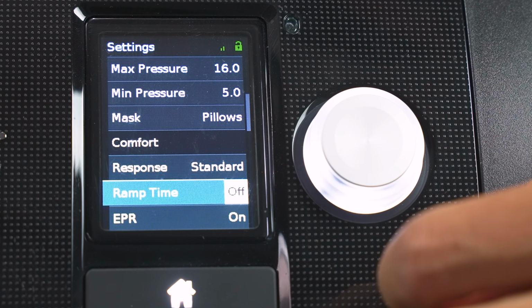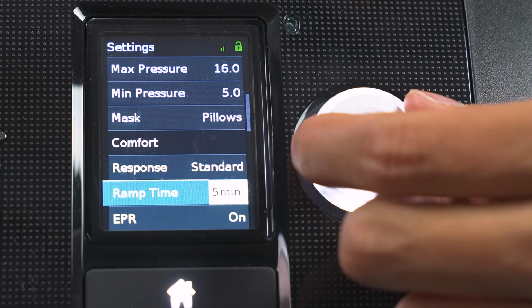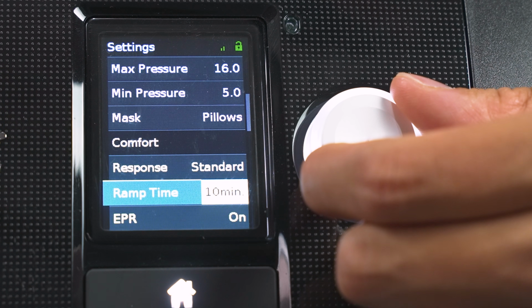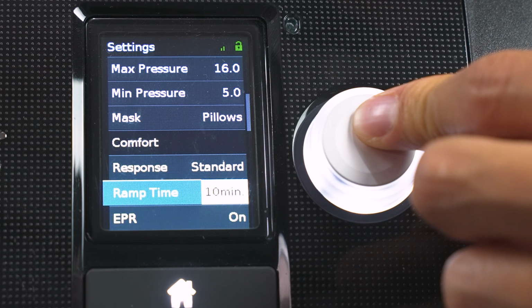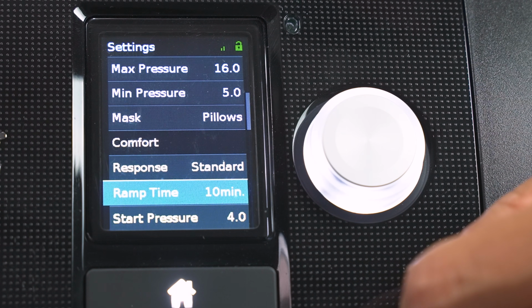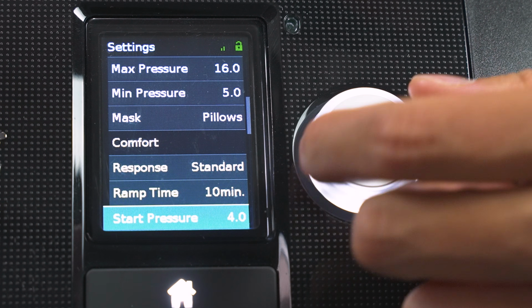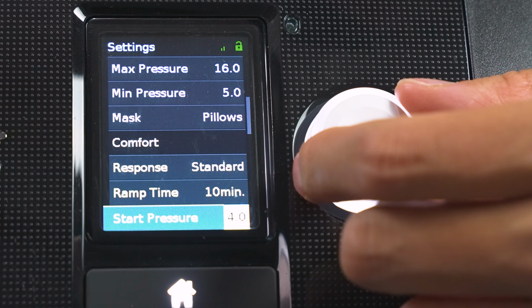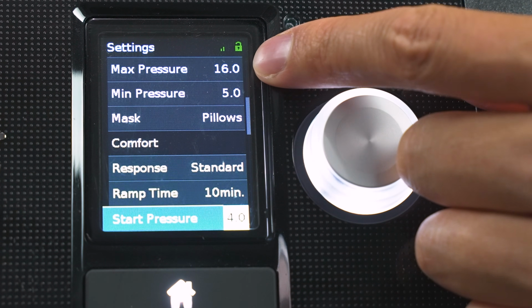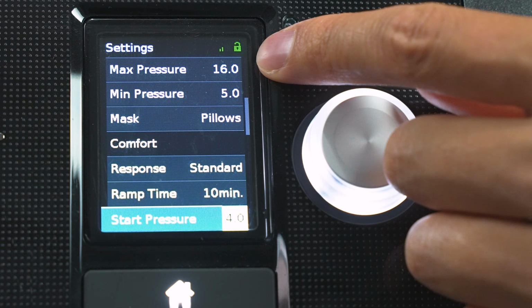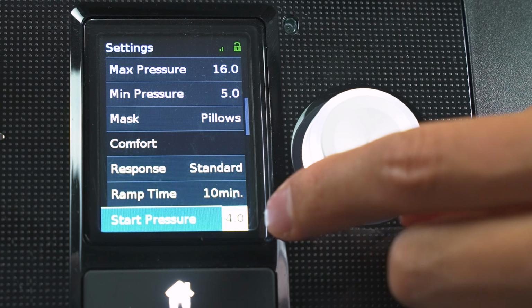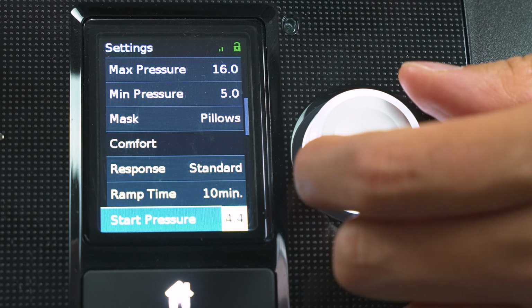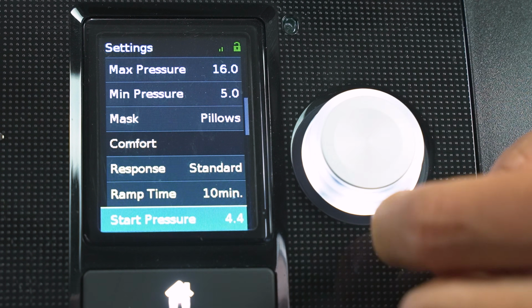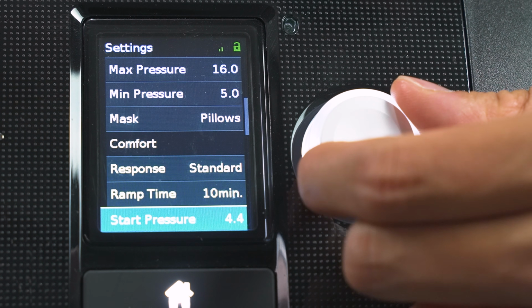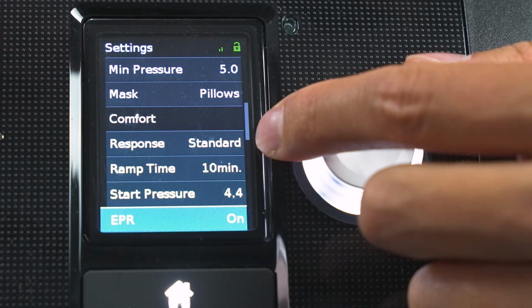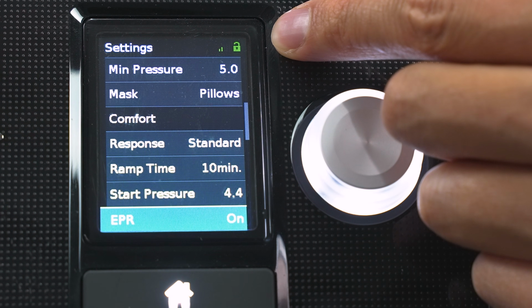Ramp is how long it takes to get to your prescribed pressure. So for example, right now it's off. And maybe I want to start at a pressure of 4, and it's going to take 10 minutes to go to my minimum pressure. So that's ramp of 10. Super simple. Start pressure, so is 4, like I said. So say I was really finicky, and my minimum pressure is a 5, so that's my prescribed pressure, but I want it to be a little bit lower than that. But say I don't want it to be 4. I'm going to have it at 4.4. So for example, in this scenario, my pressure is going to start at 4.4, and slowly over the course of 10 minutes, it's going to go to my minimum pressure of 5.